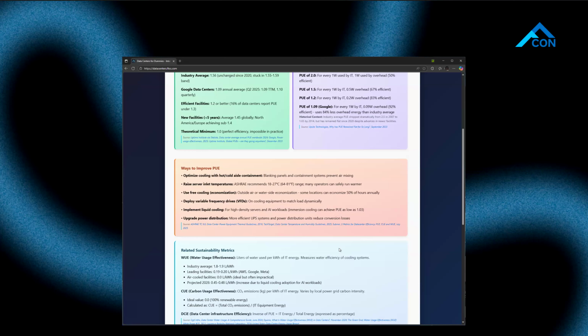That's where systems like hot containment and cold containment can also improve efficiency. But as I mentioned earlier, hot containment and cold containment are less flexible. One location I worked at previously did have a hot containment system set up, but the server racks there were a little bit unusual in that the back door of them was solid and not mesh, because at the top of the racks they basically had a chimney connecting up to the AC, so that the AC would be sucking the air directly out of the server rack rather than the server rack just venting it into the room. So in that setup, you have the AC actually pulling the hot air out of the server rack rather than pulling just the hot air that's risen to the top of the room.